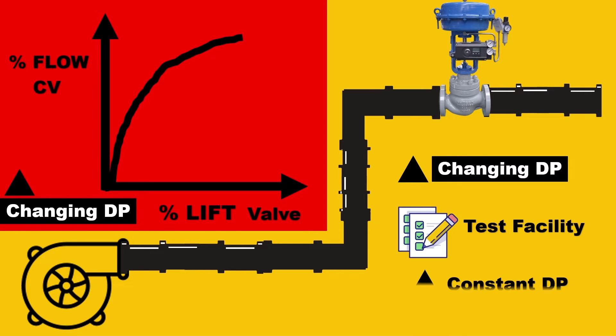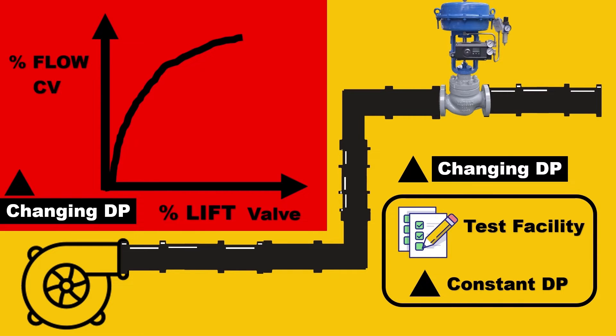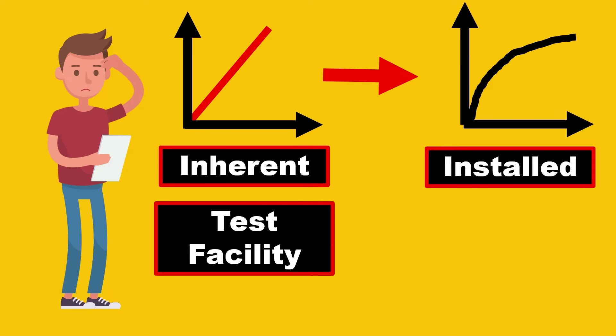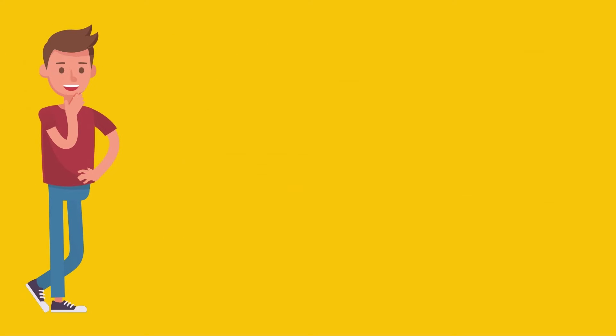The test facility had constant DP, right? This non-linearity is what we don't require. Engineers were confused that inherent characteristics were linear in the test facility, but when the same valve was put in the plant, the characteristics were non-linear. This is troublesome, but there is a very smart and creative solution.